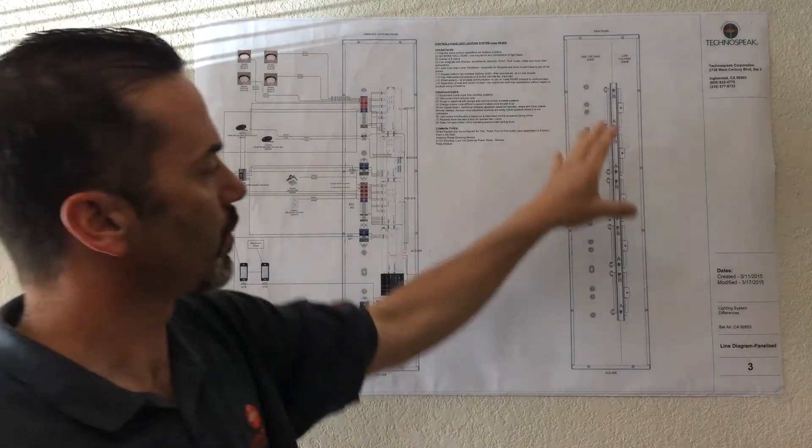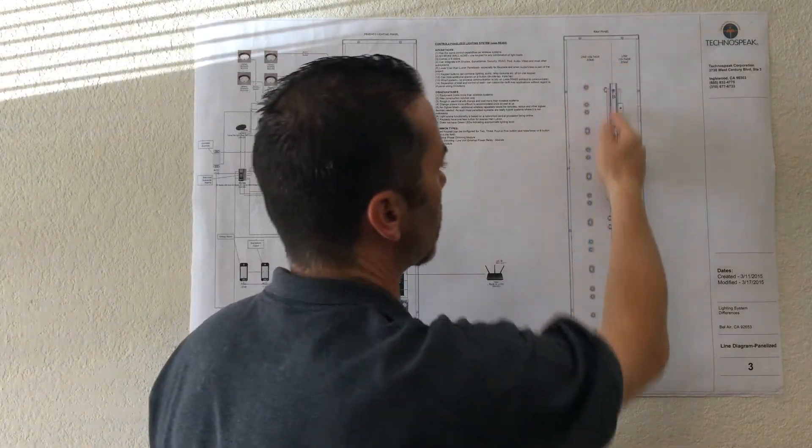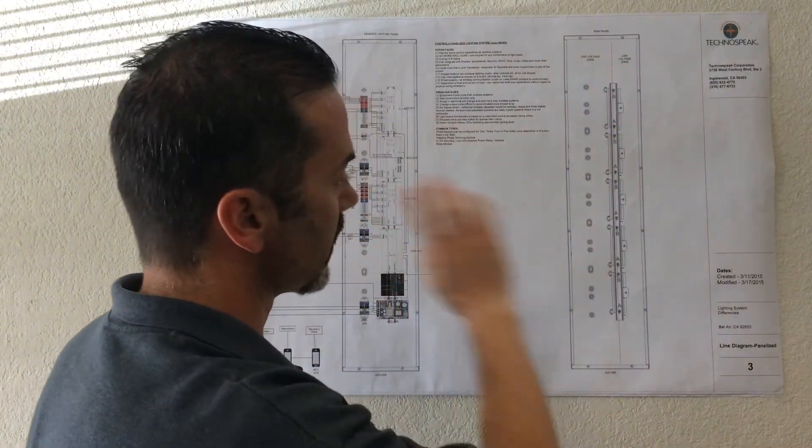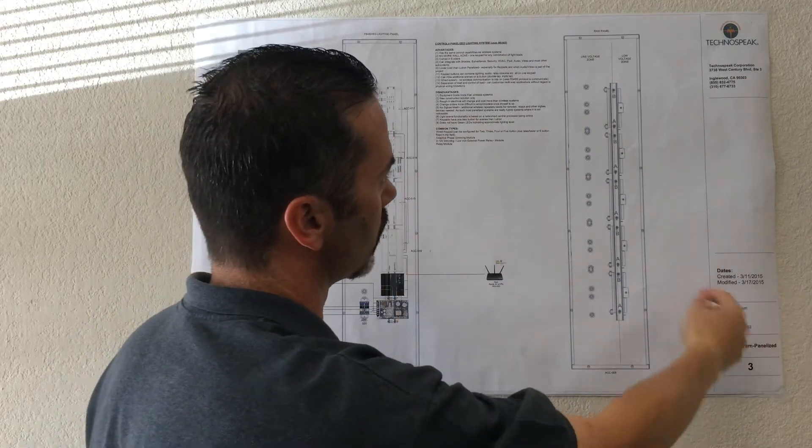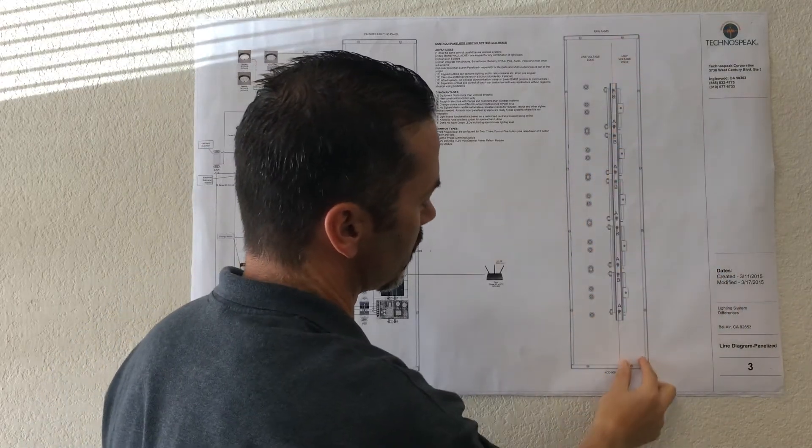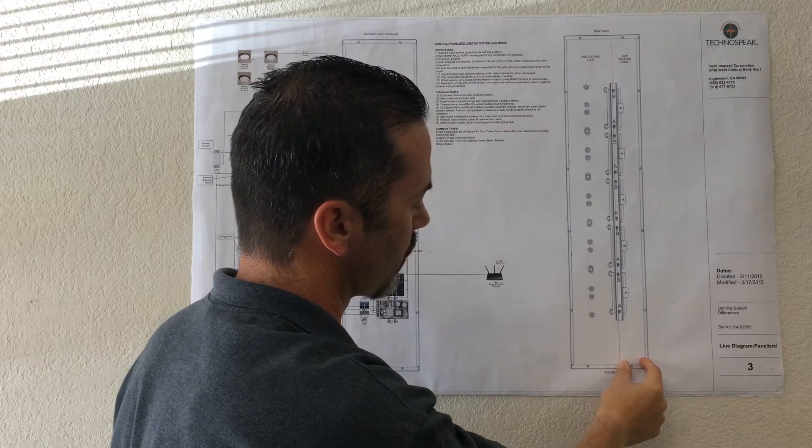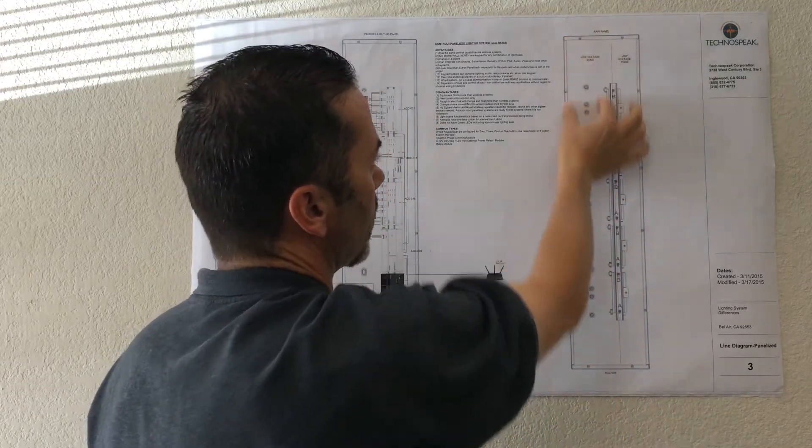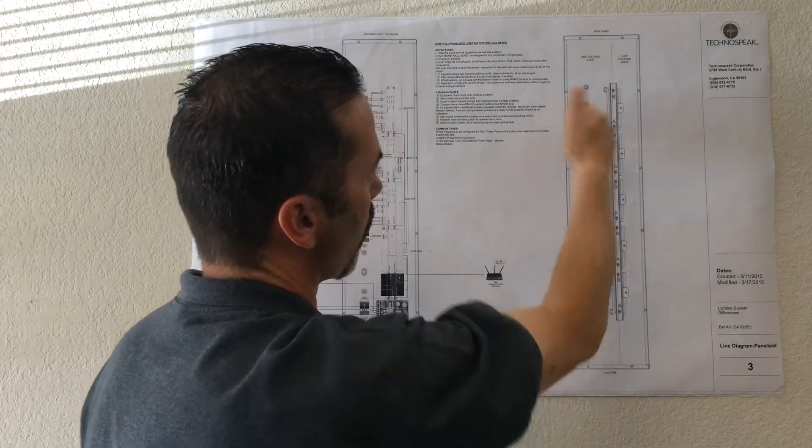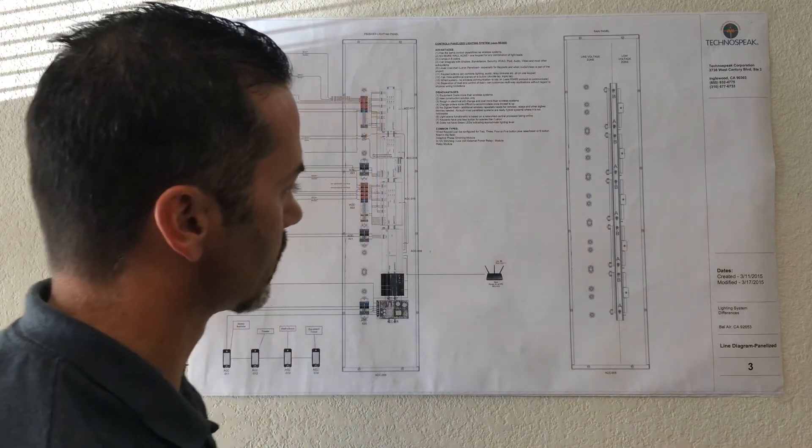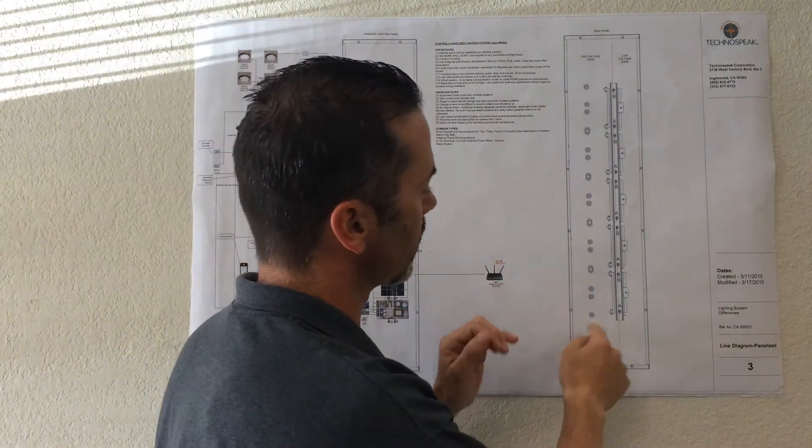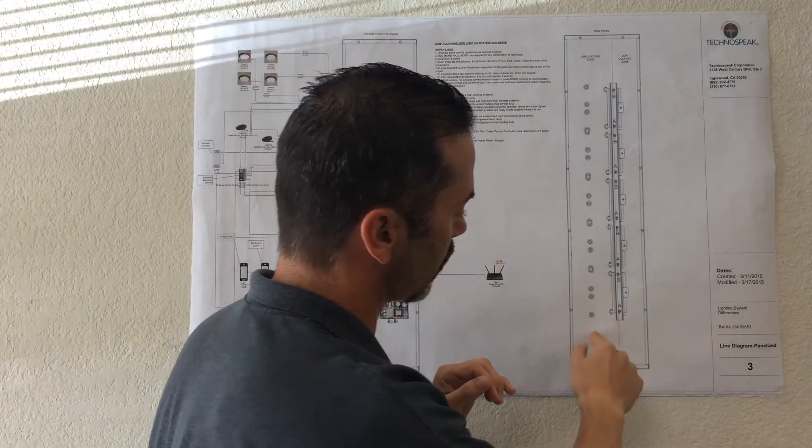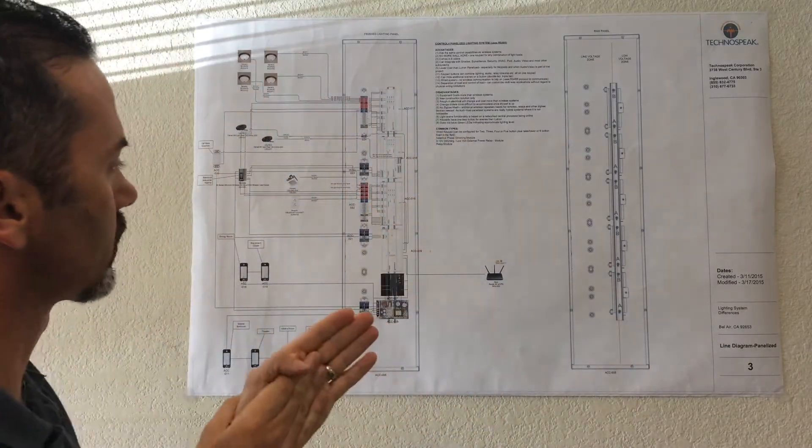So the empty panel, the main thing I want to point out is this big red line going through the middle here. That's because this panel actually has two zones. This is the low voltage zone where all the network and keypad wiring needs to get pulled in, and this is the line voltage zone where all of the electrical wiring needs to get pulled in. And you can't take line voltage to this side, can't take low voltage to this side, so just want to make sure that's clear.